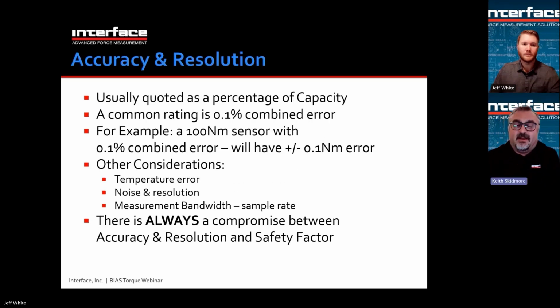So accuracy and resolution. Usually quoted as a percentage of the capacity. So say it's a 100 Newton meter sensor. There's a combined error of 0.1%. That would mean 0.1% of 100 Newton meters, and that would be a plus or minus 0.1 Newton meter error. Now, that's great, except a lot of times you may want to use a 100 Newton meter sensor to measure 5 Newton meters. And you might need to do that because of other extenuating circumstances in the application. So that is one thing to consider.